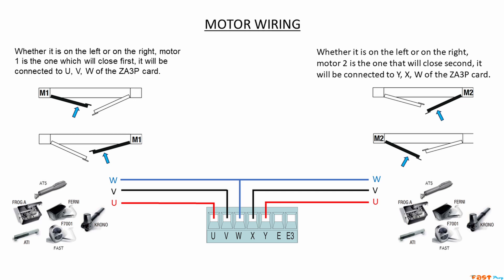Once the motors are connected, you'll need to check if the phases are wired correctly. To do that, when the setup is done and the motors are running, place the gates halfway open, cut the power, and then turn it back on.